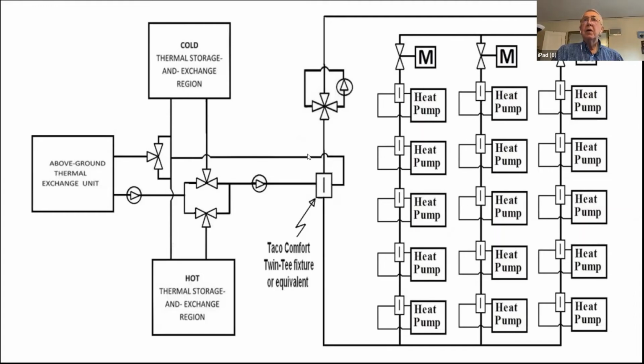So right here now, instead of a single heat pump, which was in this region, we have a device which is called the Twin T fixture. It's a passive device. It has 4 water connections. It has 2 relatively small pipes coming in horizontally here, and 2 larger pipes coming in the vertical path. So it's kind of like what's called a hydraulic separator. It allows a different flow rate on the left-hand side compared to the flow rate in the vertical path pipe here. And that's very beneficial.